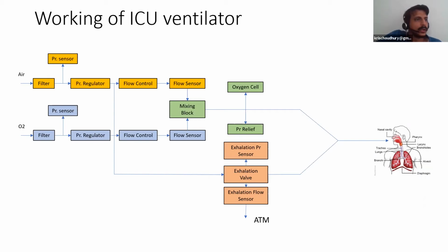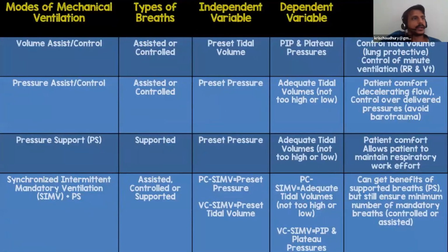After this, we get on to the breathing modes. There are predominantly 4 modes here. First, there is the volume assist control mode. In volume assist mode, you have a preset tidal volume, and only that is taken as input from the doctor. Other pressure curves and pressures are not controlled by the doctor.